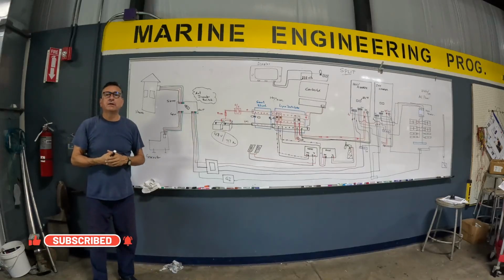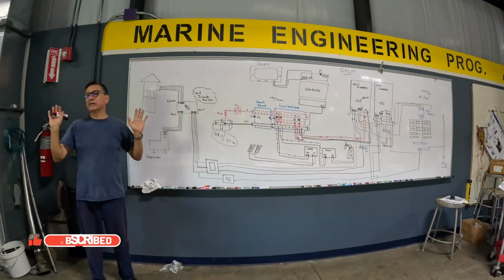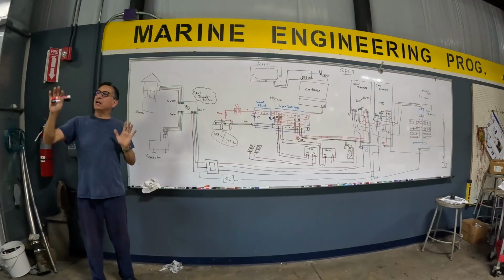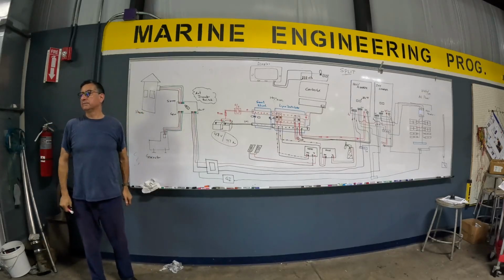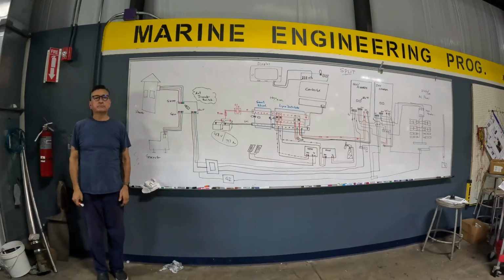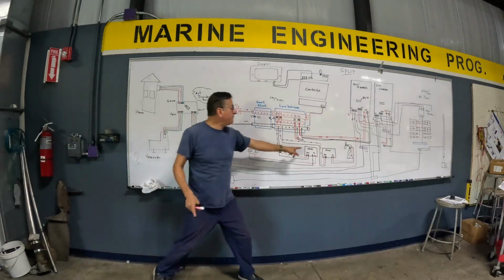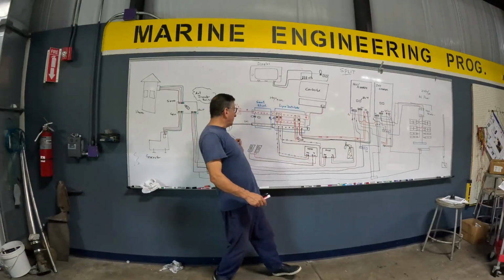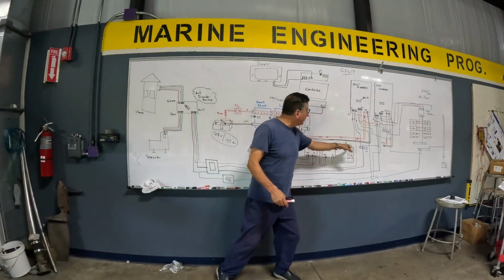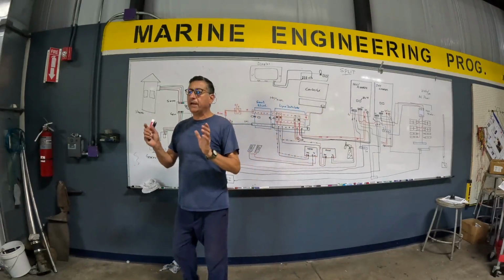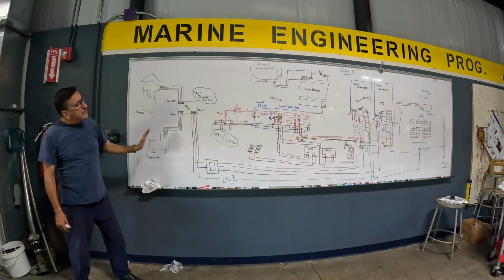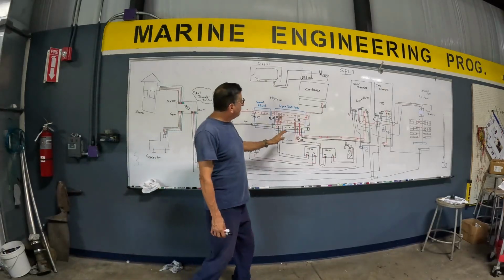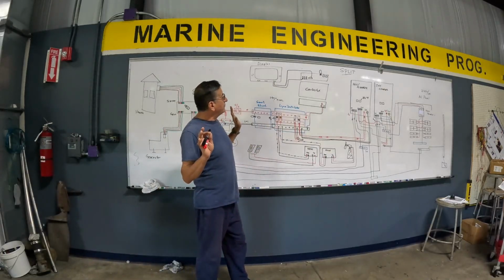That's okay? I can connect the groups of solar panels that I want. If they are connected independently, try to use independent MPPTs. Never try to use the same MPPT to connect the input of the solar panels and the input of the windmill. No, separate MPPTs.